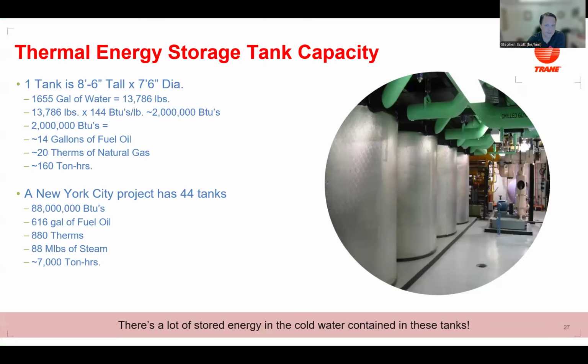Well, what about using thermal batteries? This is what they did in Manhattan. They used tanks, and just to give a little more information on the tanks, 7.5 feet wide, 8.5 feet tall. Each tank, when you change the phase, when you either melt or freeze ice, holds about 2 million BTUs of energy, or about 160 ton hours. So a lot of energy is stored in this water, and 3 of them will take up 1 standard parking spot. So they don't take up a huge amount of space, but when money incentivizes that, that can certainly be a game changer. Or if companies have decarbonization targets, that can help move things along as well. So how does this work as a storage source on the next slide?